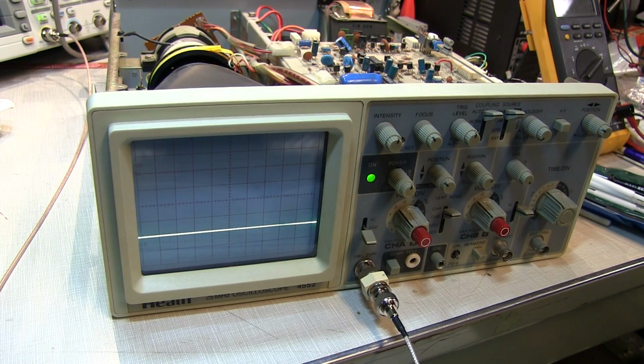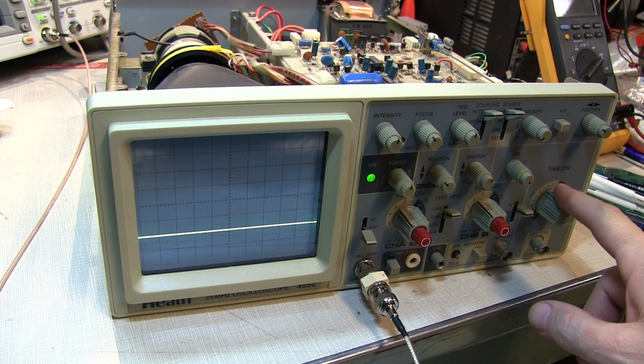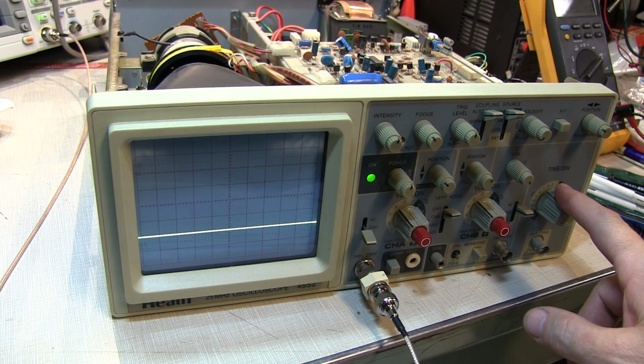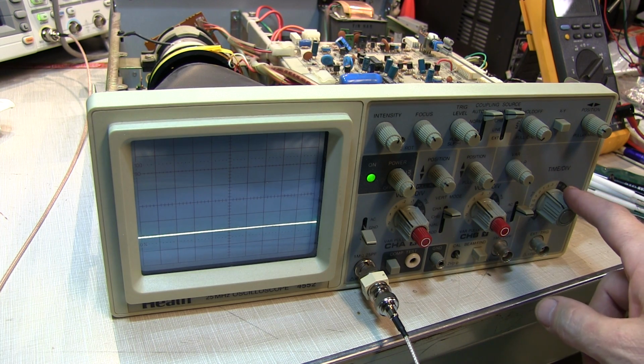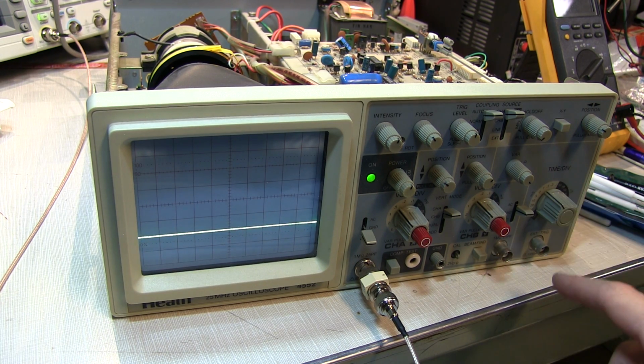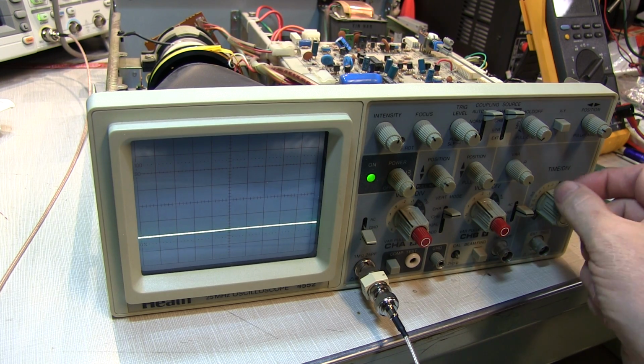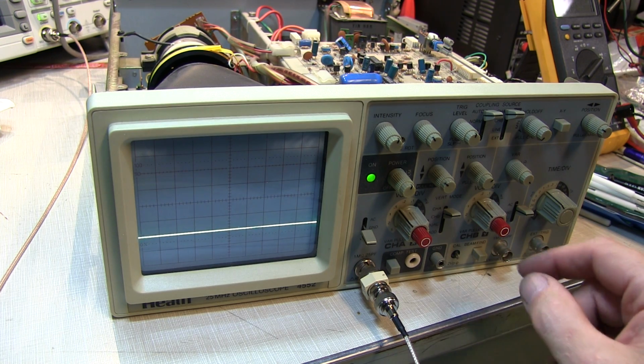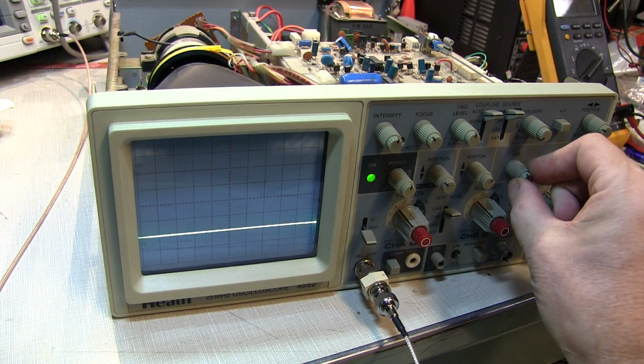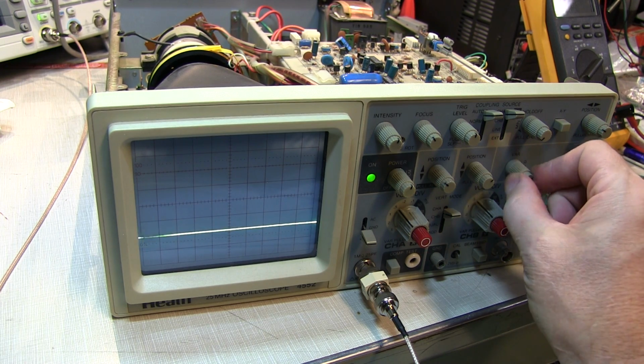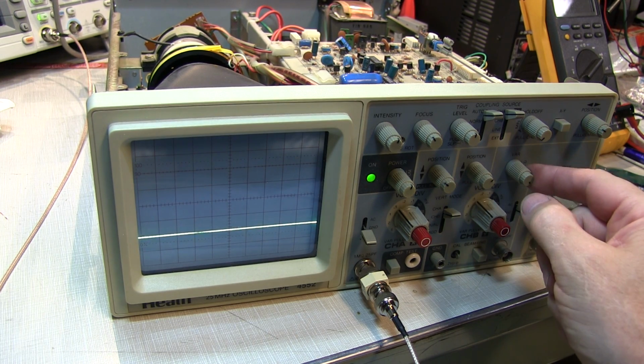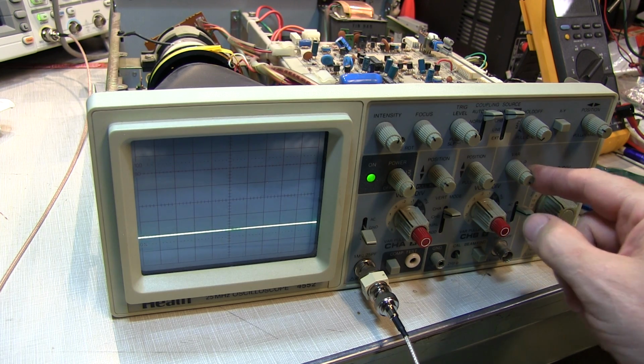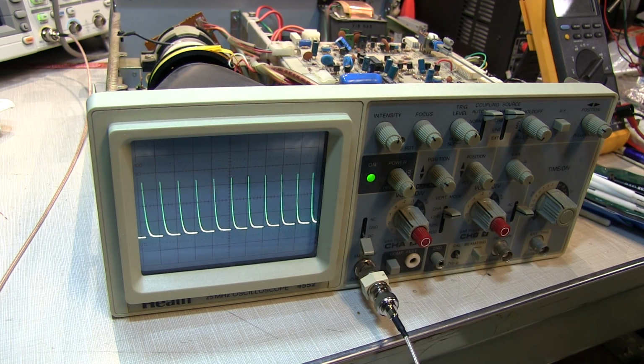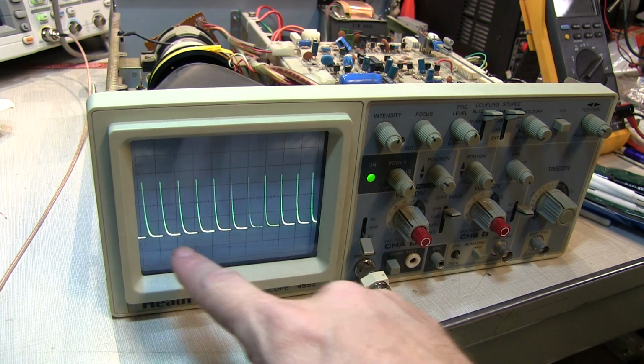The last section to adjust is the horizontal time base accuracy, and that needs to be done at 2 different settings. There are 2 different controls for that, as well as in the ×10 horizontal magnification. So the first thing we want to do is ensure that the variable control is all the way fully clockwise and in the calibrated position.